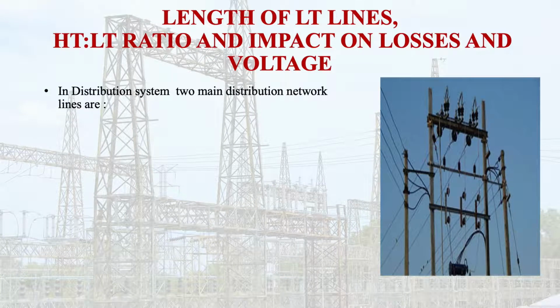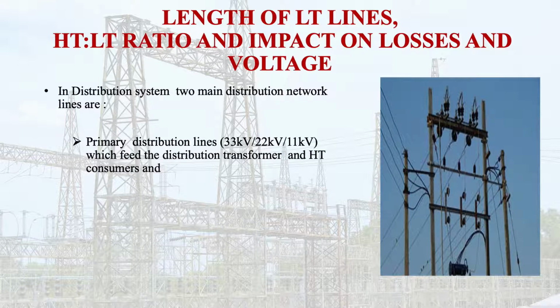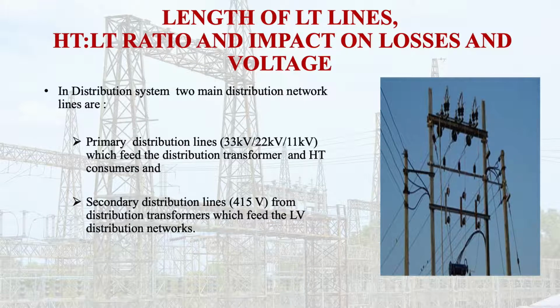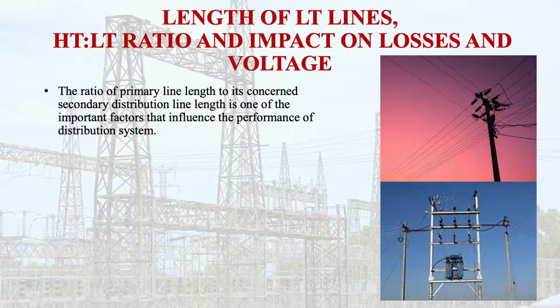So learners, in the distribution system, there are two main distribution network lines: primary distribution lines and secondary distribution lines. Primary distribution lines, 33 kV, 22 kV, 11 kV, feed the distribution transformer and HT consumers. Secondary distribution lines, 415 volt or 400 volt, from the secondary side of the distribution transformer, feed the low voltage distribution networks, the last link connecting the consumers. So the ratio of primary line length to its concerned secondary distribution line length is one of the important factors that influence the performance of the distribution system.